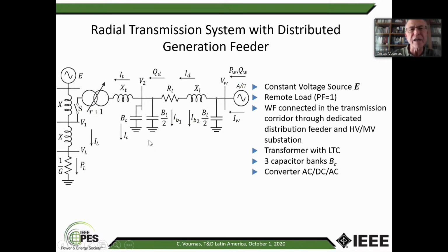And as I said, in Greece, it is customary that in each such feeder, the TSO requests that the wind producer has installed 3 capacitor banks, 4 megavar each, which are connected according to instructions given by the TSO control center. And of course, the wind farm is not like a synchronous machine. It's connected through a converter, and we assume that it is fully controlled, active and reactive power. The active power is controlled to produce exactly the power given by the wind, PW, and the reactive power is controlled based on 3 systems that we will discuss later.